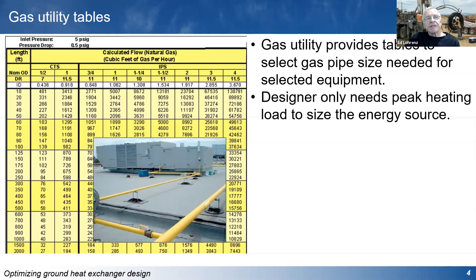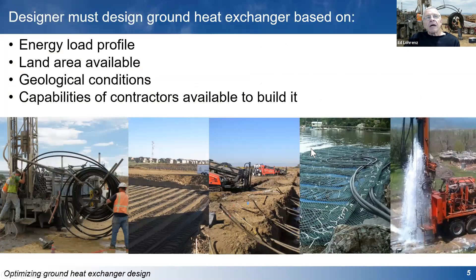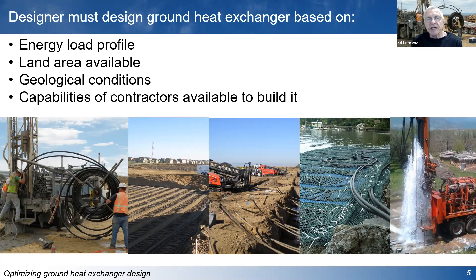If it's a gas line, the gas company has charts and tables available. All you need to know is the peak heating load, and you can select the gas pipe size based on how many BTUs you need to deliver on the coldest day of winter. But with a ground source system, you really have to design the energy source as well as the equivalent of the cooling tower. There are a lot of different options, and that's one of the beauties of this industry. It really depends on the land area available, the equipment available to install it, the geology you're working with — all of those things impact how you design the ground heat exchanger to optimize the performance of the whole system.